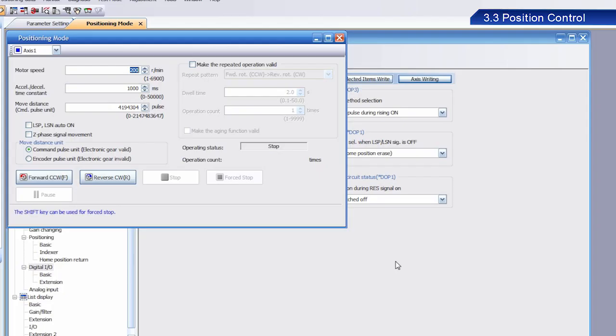Now, I would like to describe the Move Distance setting. As the name implies, this setting sets the amount of movement. For this positioning control exercise, enter the actual distance of movement. Set Move Distance with a value of 4,194,304.